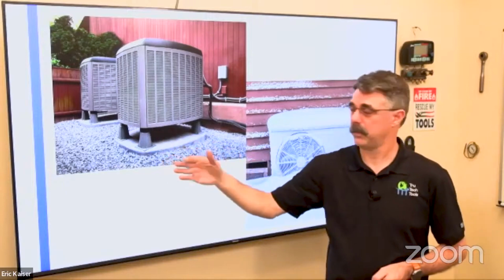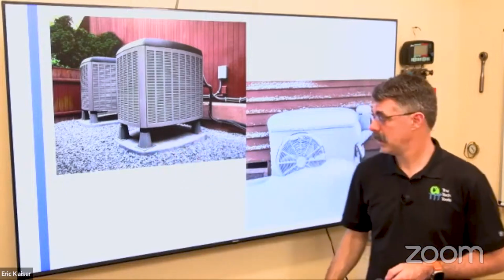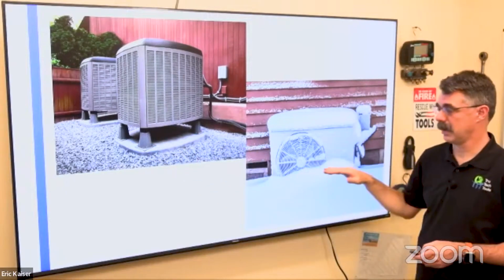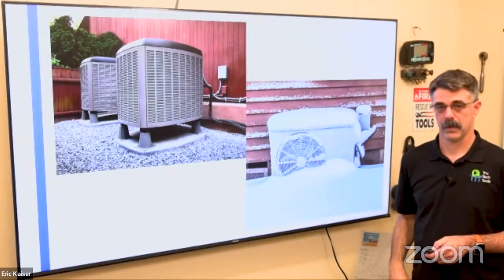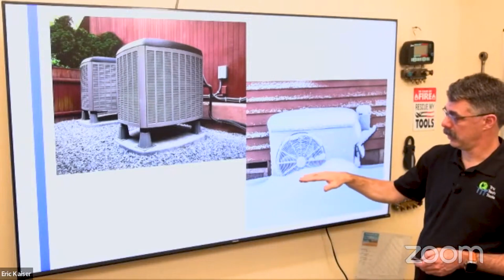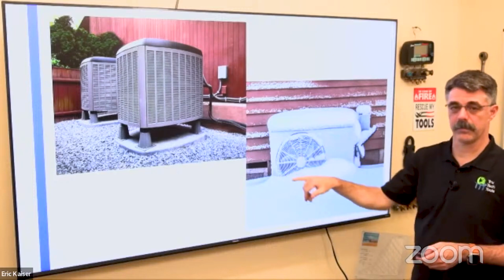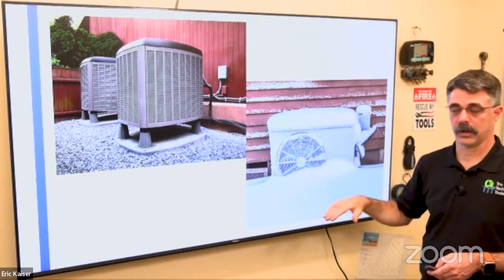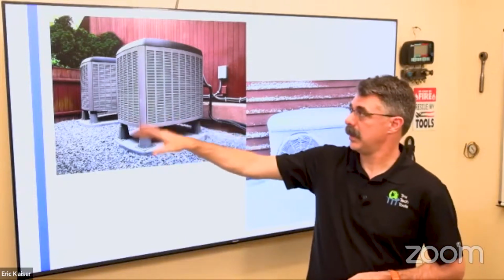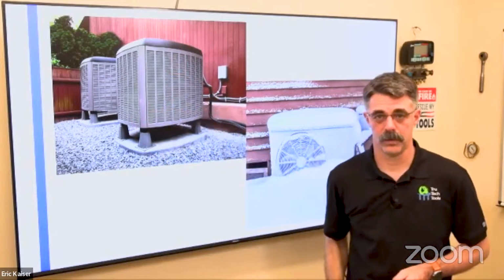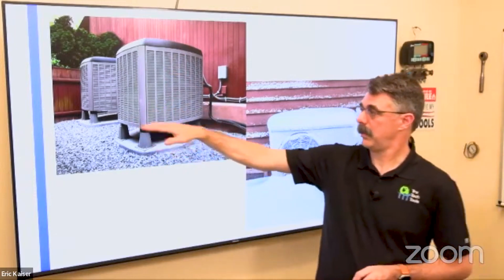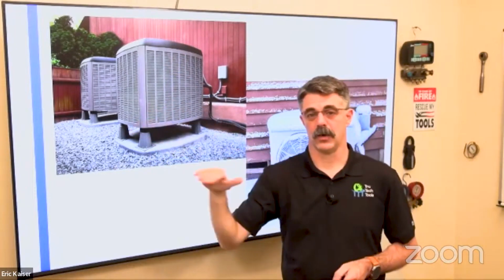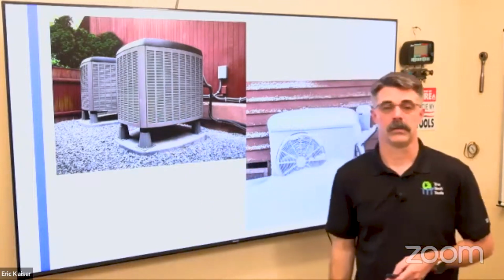It's really easy to put them up on what's called pump ups or legs, and we also need to make sure we get them up above the snow line, because we don't want snow stacking up in front of the fans anywhere up beyond the bottom of that unit. If we have an updraft unit like this one, we don't want that snow coming up in here and catching and holding water in the bottom of there.